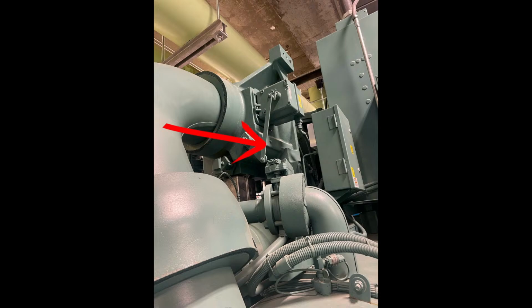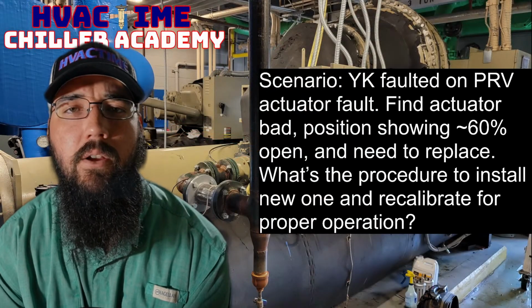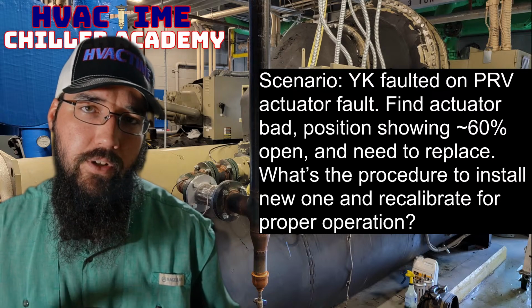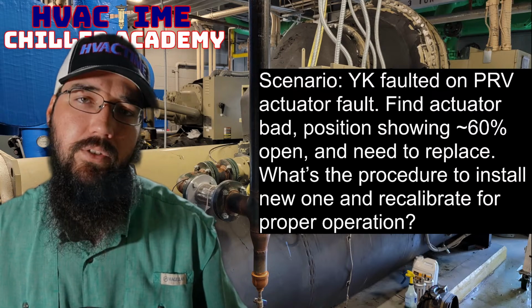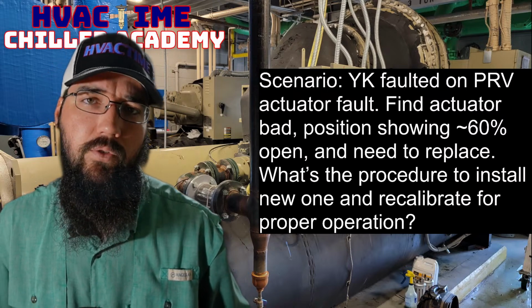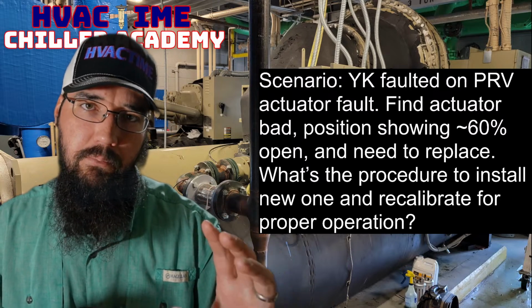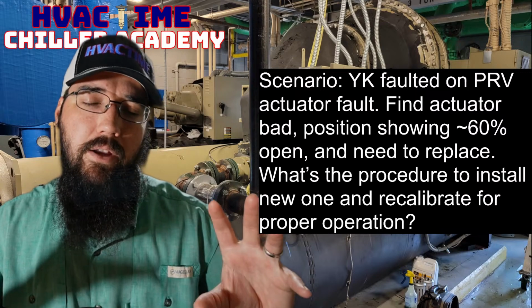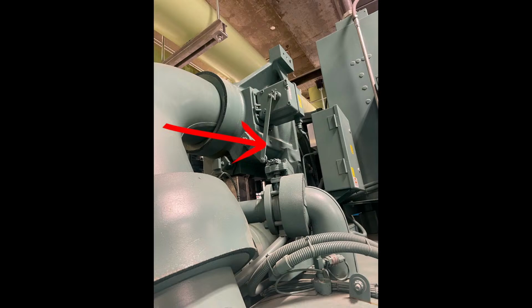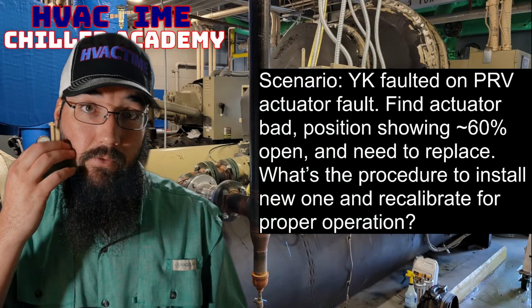So when we get into calibration, with the machine off and the unit switch set to off, you have to make sure that's in the off position, and I'm pretty confident you have to be in the service mode to do this. With everything positioned and the sensor mounted, the position sensor, which is this little box right here, has a rheostat in there that's sending a resistance back to the microboard. As the microboard reads that resistance, it knows that X ohms is X position, Y ohms is Y position, there's my 0 and my 100, and then I'm on a linear scale in between, giving me the physical position of the PRV shaft.